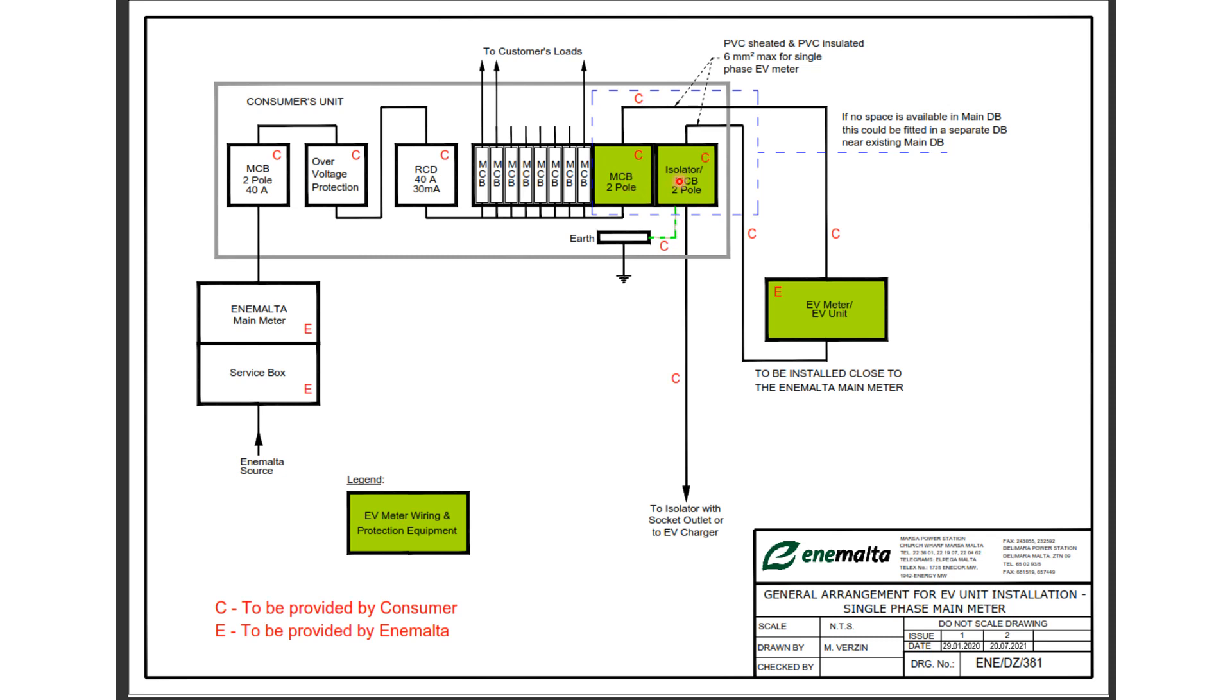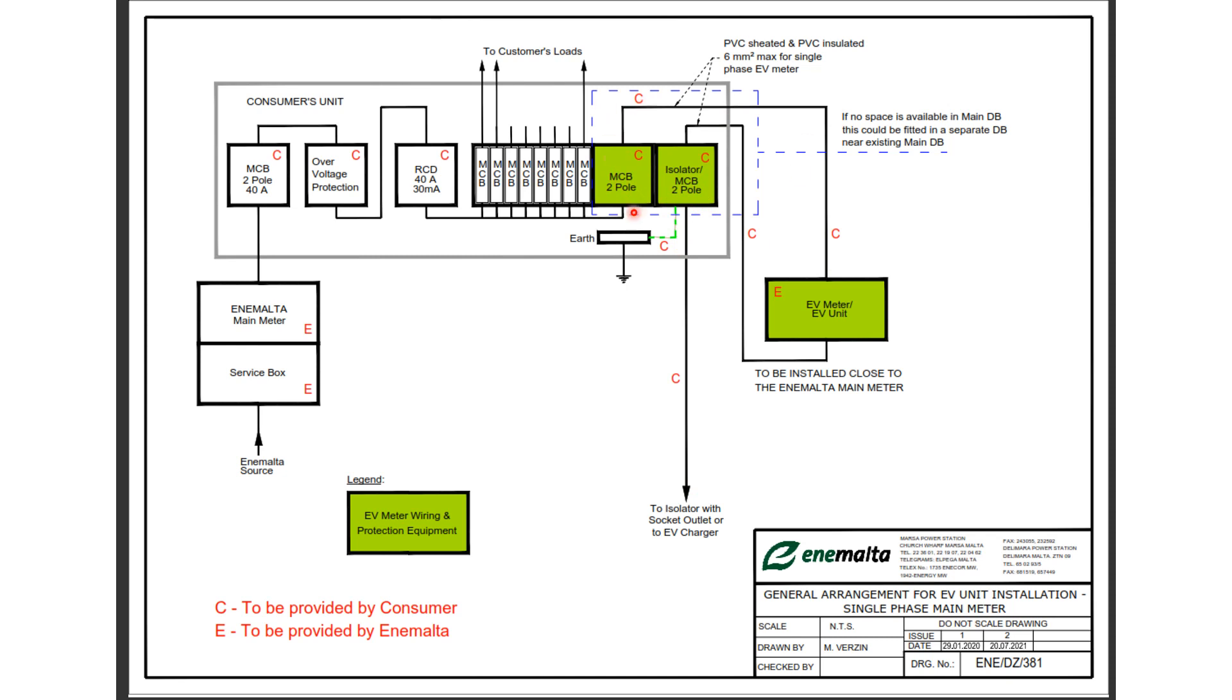Basically, here you are switching the supply to the meter and here you are isolating or switching off the actual charger. Now the second device can be an isolator, there is no need for it to be an MCB, because the circuit is already protected by the two pole MCB before the EV meter unit.